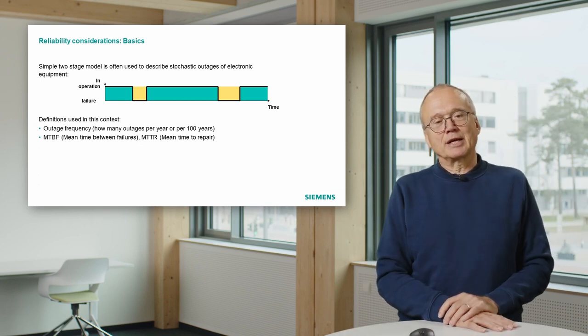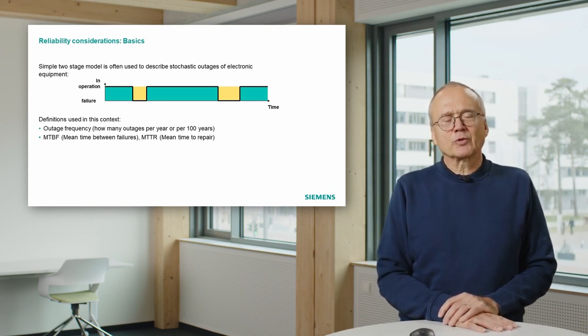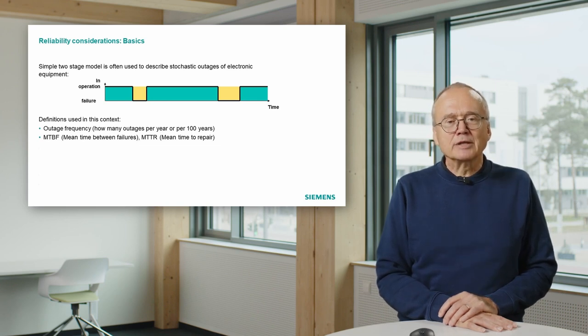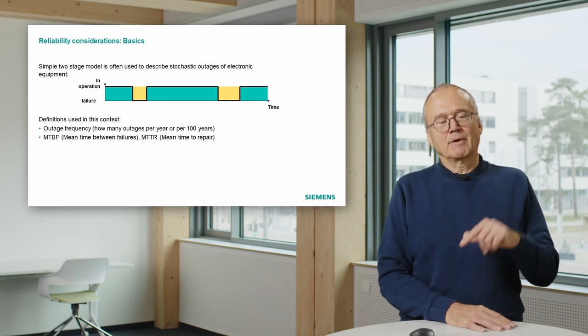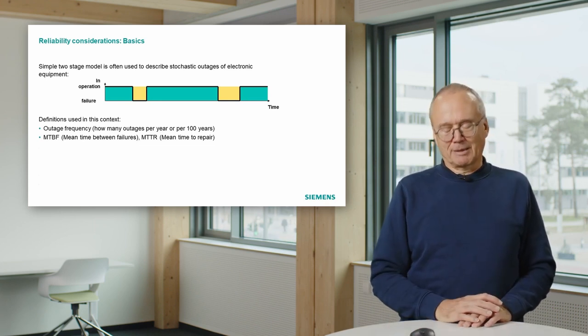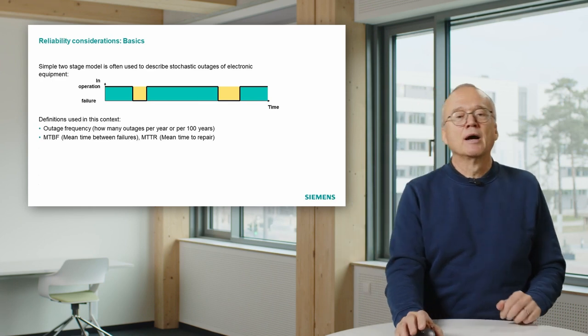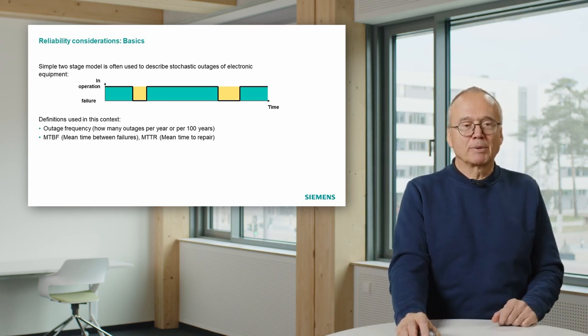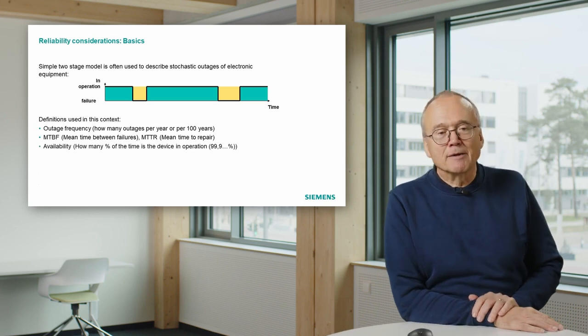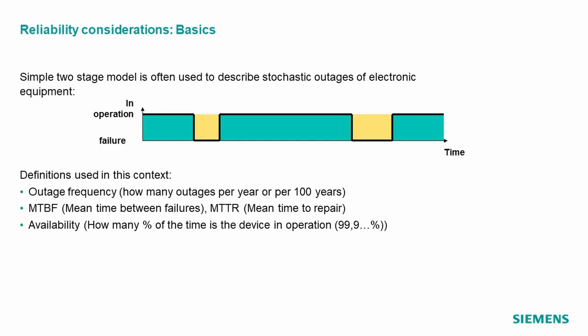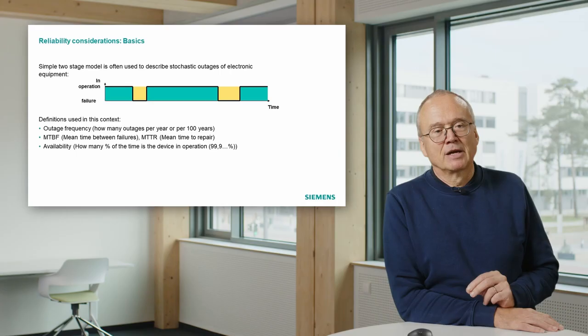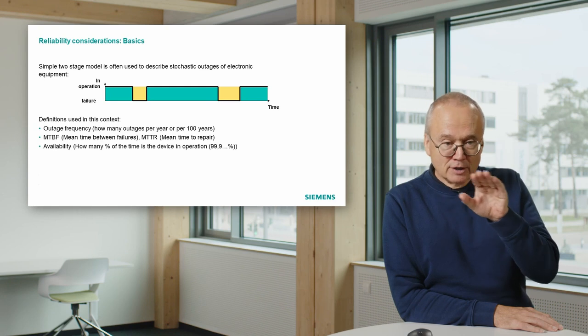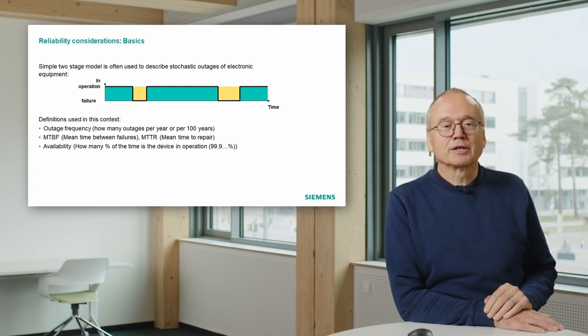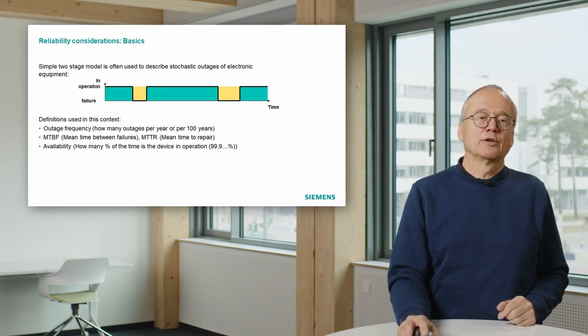I personally think that these calculations are not really relevant for our field of application, for our protection field. I will explain the reason later, but that term is sometimes used. Another thing is the mean time to repair. How long does it take to repair or to replace a device? And then you have the so-called availability. That is a figure which is typically something like 99.9%. That is the percentage of the time where the device is in operation. So these quantities are defined for simple electronic devices which can either be in operation or defective.